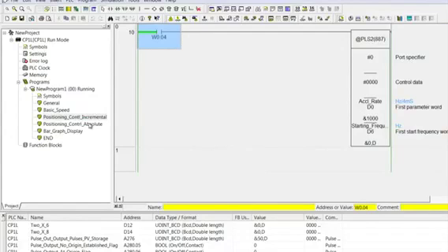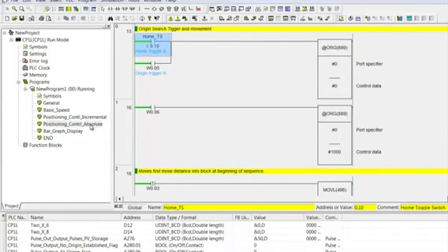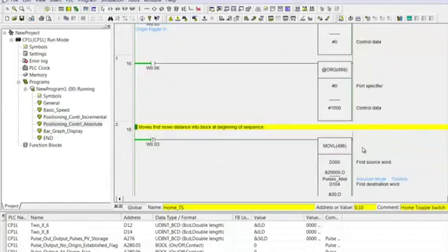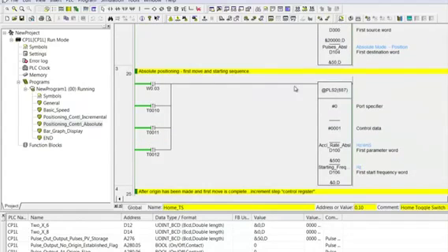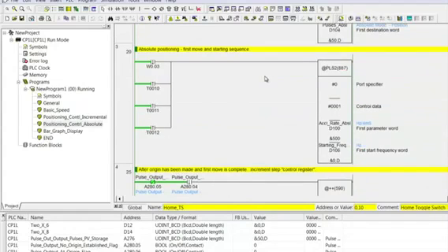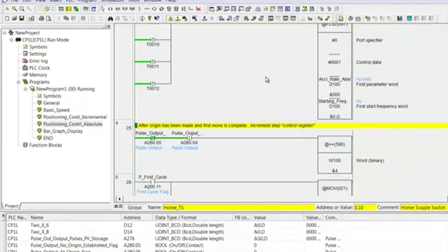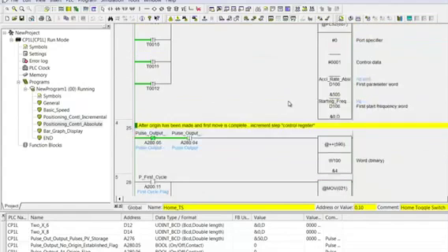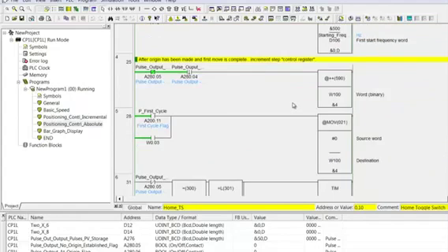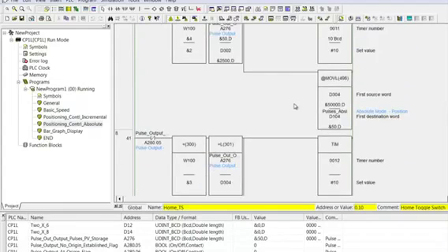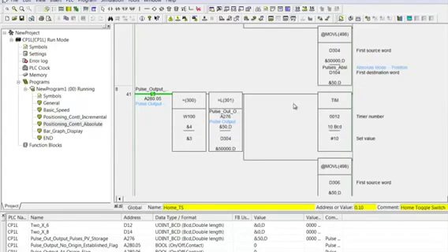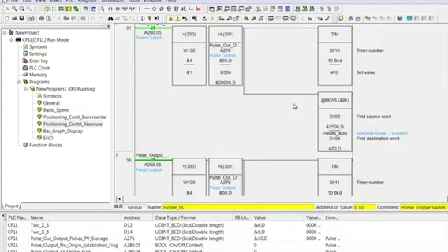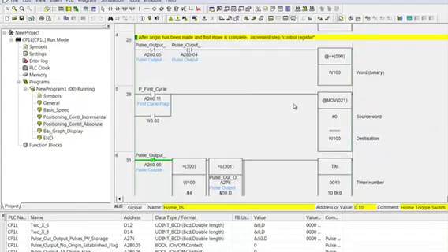The sequence that I ran for you just a few minutes ago under the absolute move with four positions. I've got to establish a home, a home position first, and that's done with an origin command. There's an origin return, and here's an origin search. You can just see that the control data is a little bit different. I've got some move data in here to set up a beginning block for the move sequence, and then I've just got a pulse two instruction that takes in different move values. So I've just got three or four rungs of code that are required to move that sequence of four moves. Really very simple.